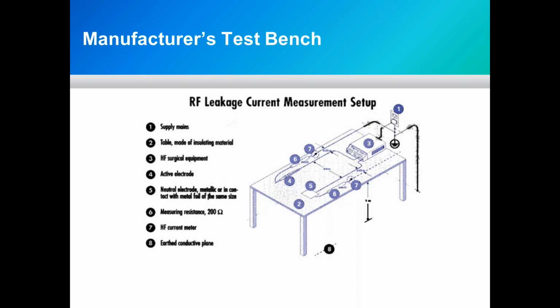Fortunately for biomed testing in our labs, we don't have to duplicate all of this. What we do need to do, though, is make sure our leads are relatively short as possible and that we don't have any coils, any inductance. We don't have our test cables laying across chassis and such, which could add capacitance that would impact our readings.